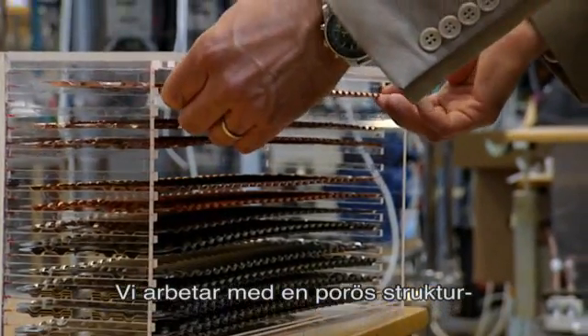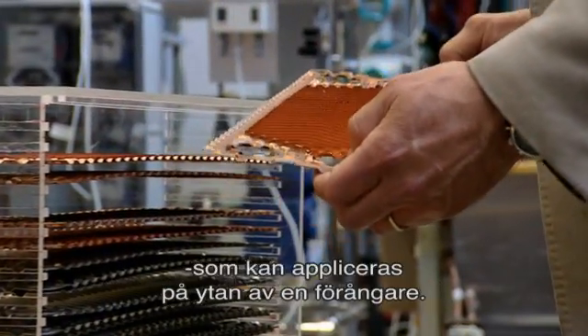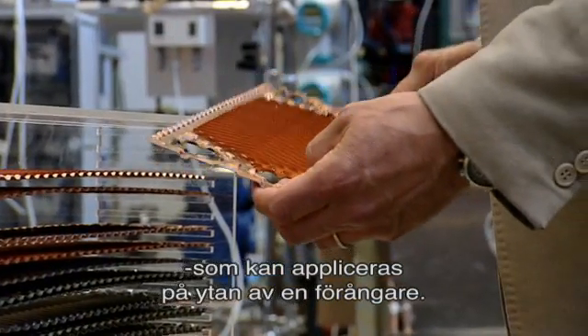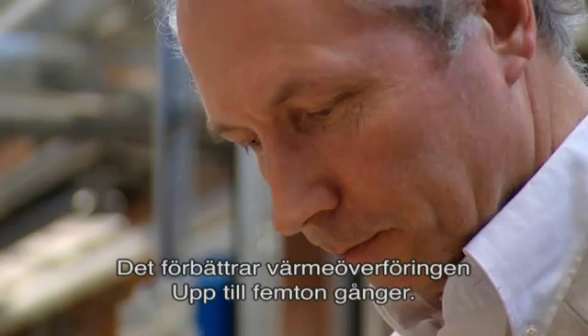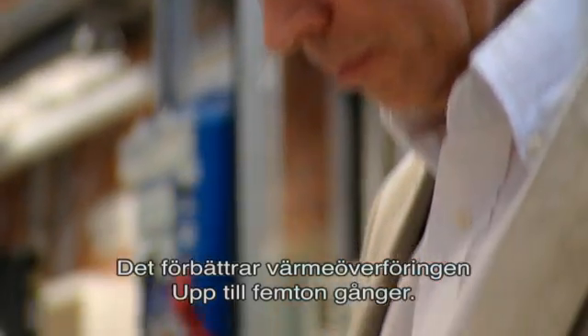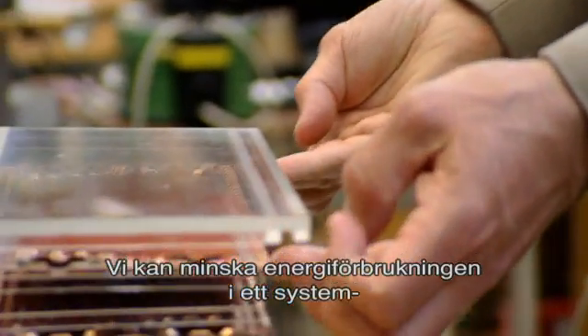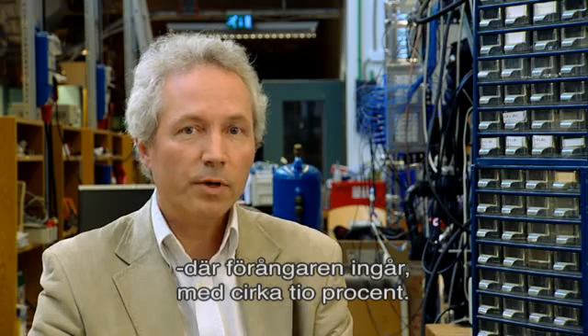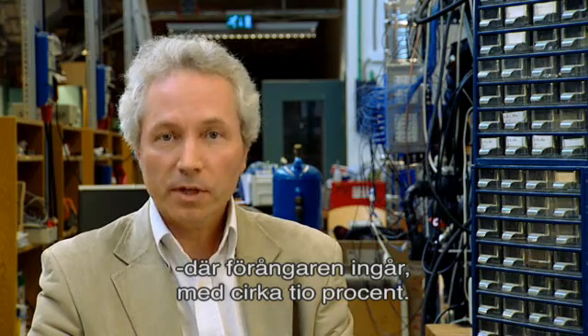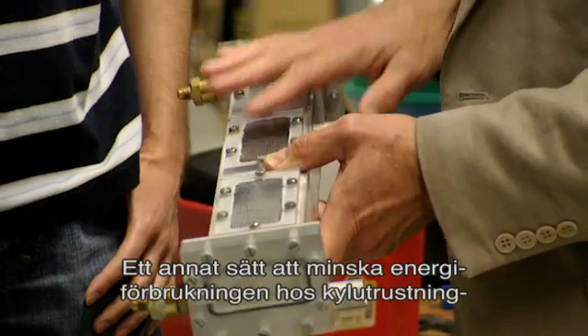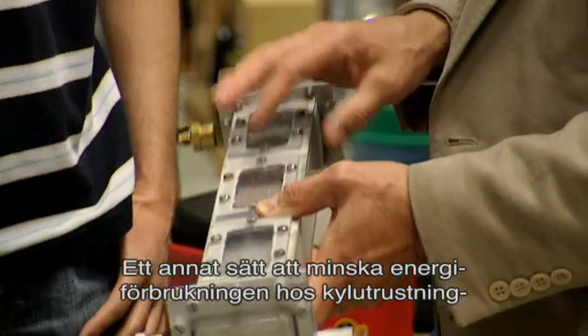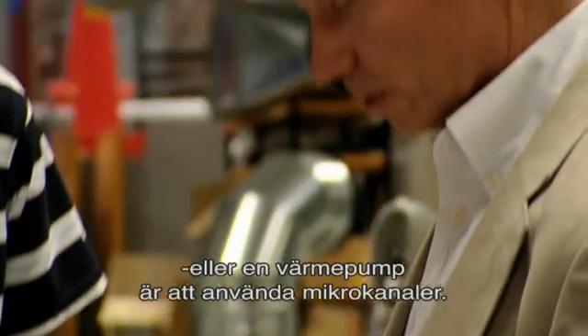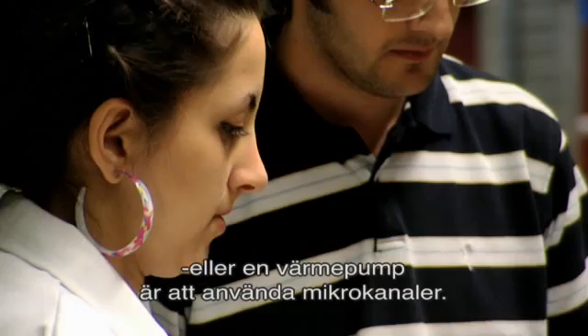In our lab, we are working with a porous structure that can be applied to an evaporator surface, which enhances heat transfer by a factor of 10 up to 15. This allows us to reduce the energy demand of the system that the evaporator is part of by about 10%.